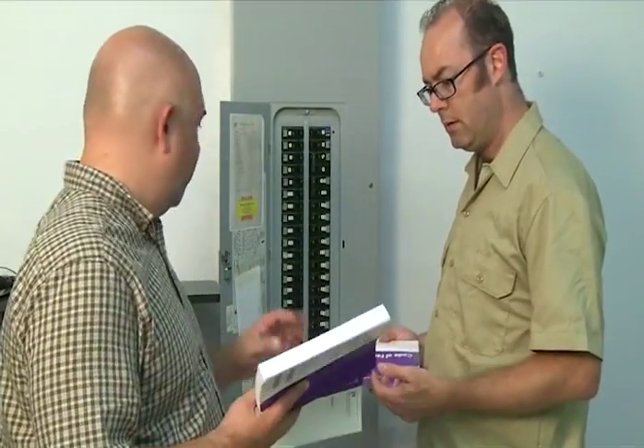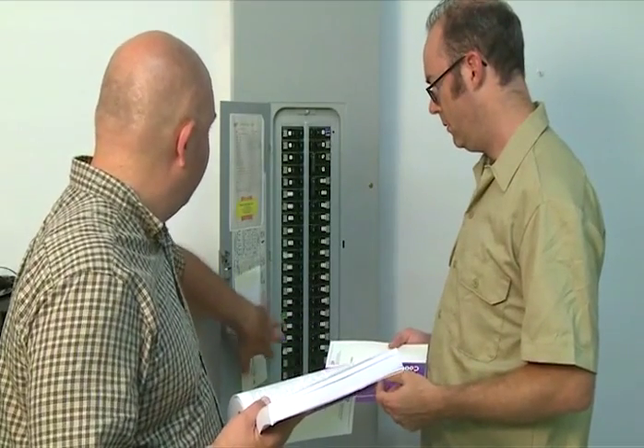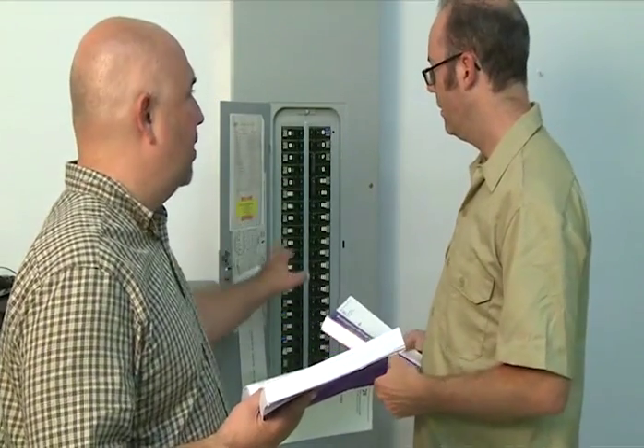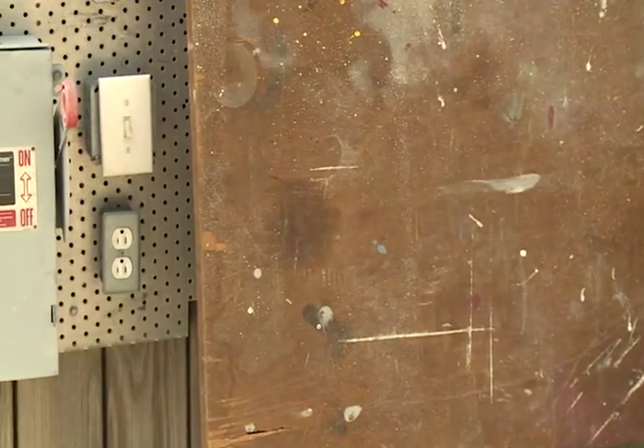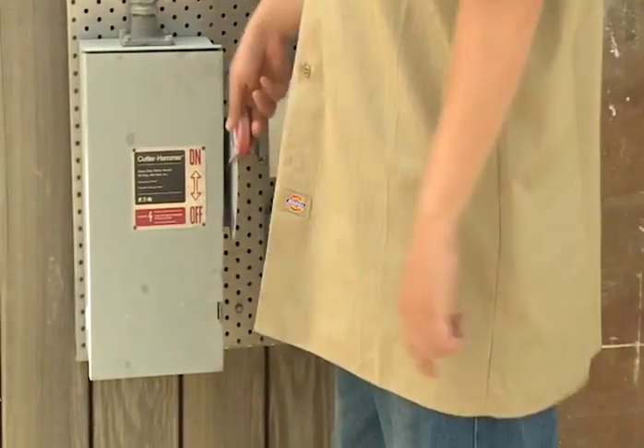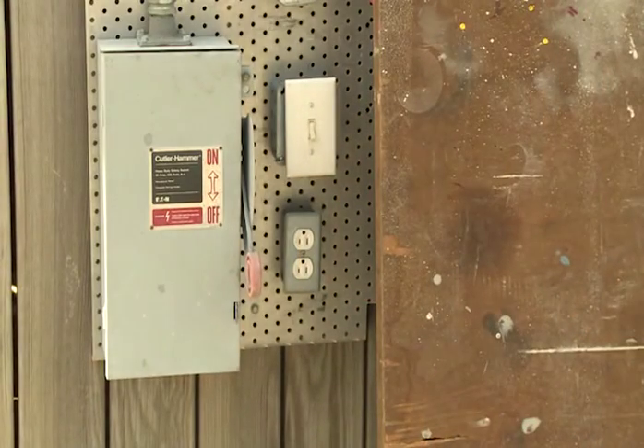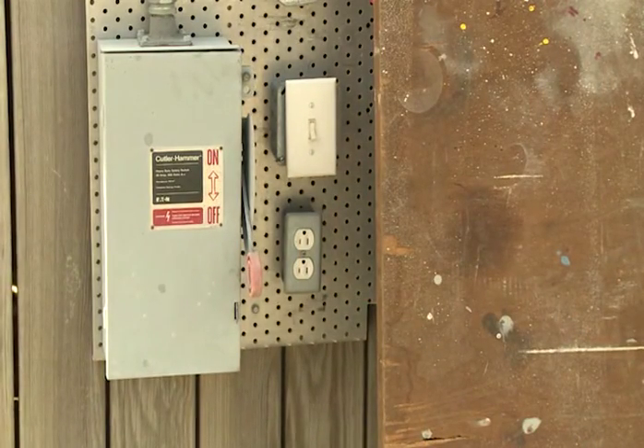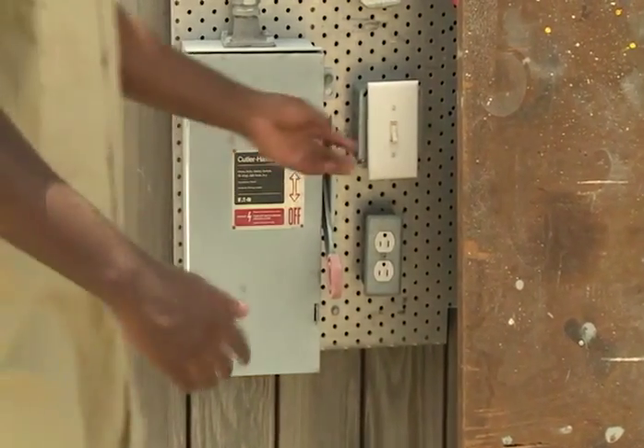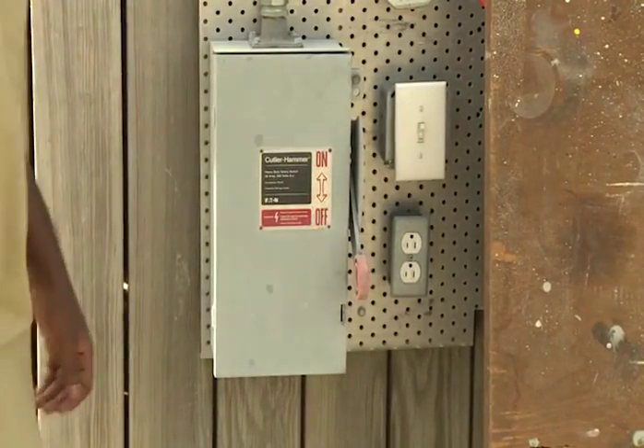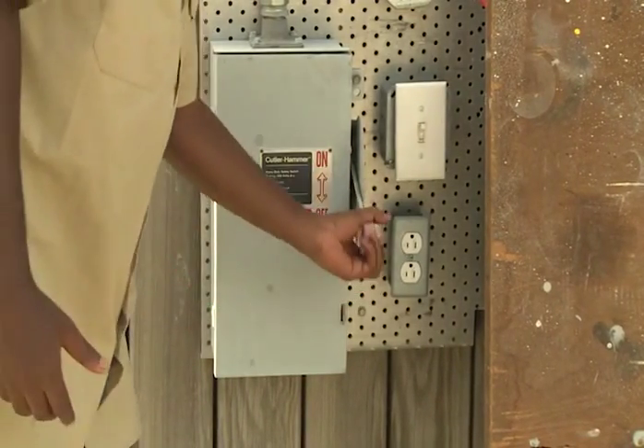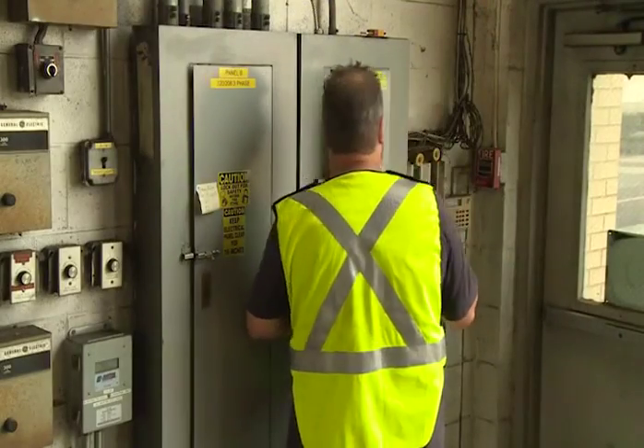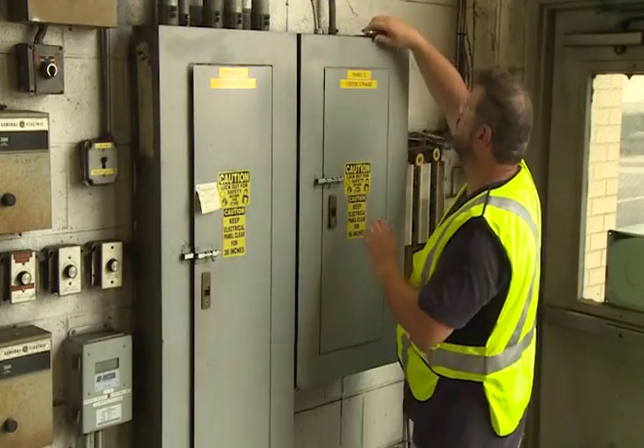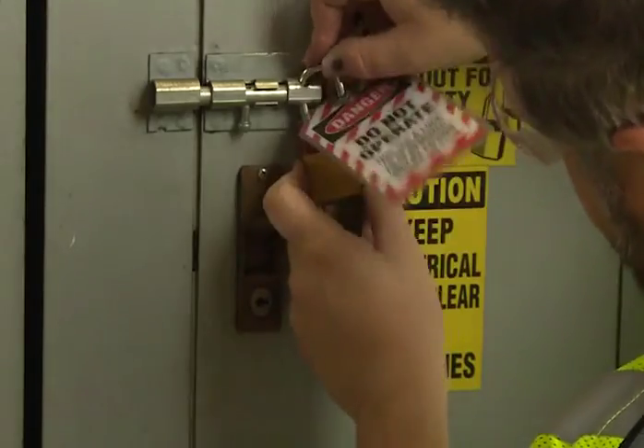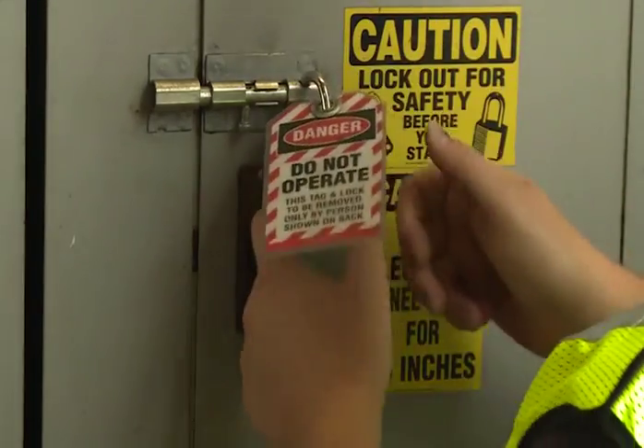Preventing electrical accidents also requires stringent adherence to safe work practices in every step of the work that is being done. For example, the equipment to be disconnected may be located at some distance from, even out of sight of, its power control system. Once the energy has been turned off, it is all too easy for someone who can't see people working on the equipment to turn the electricity back on unexpectedly. That's why the power control system must be locked out and tagged after being turned off. This physically prevents the equipment from being re-energized.